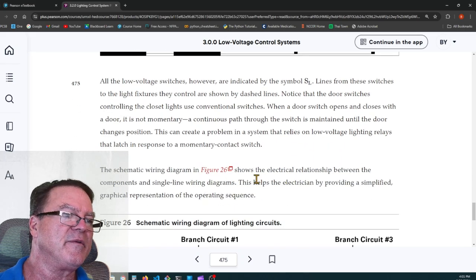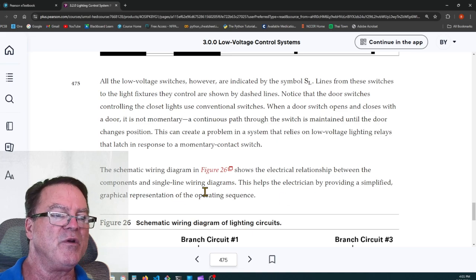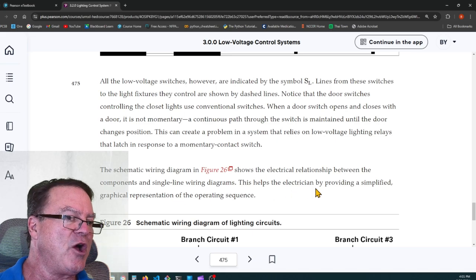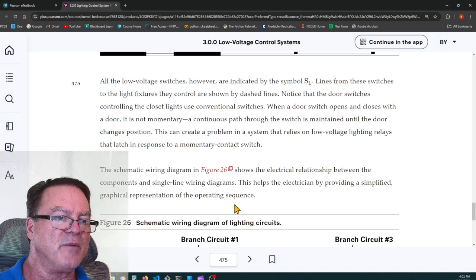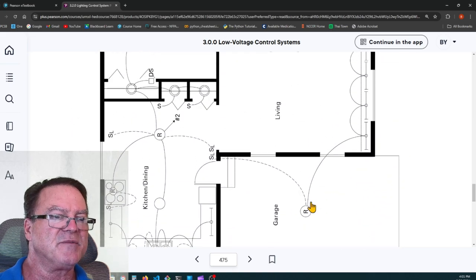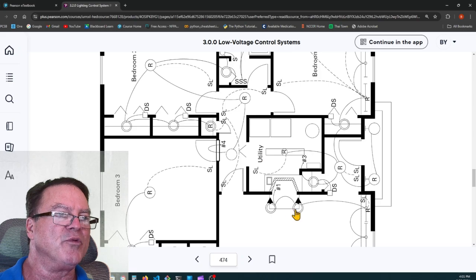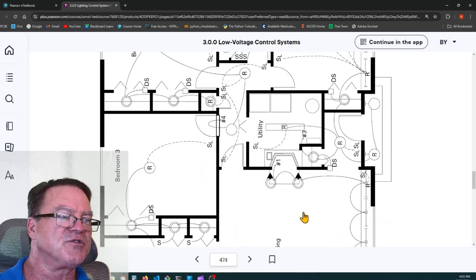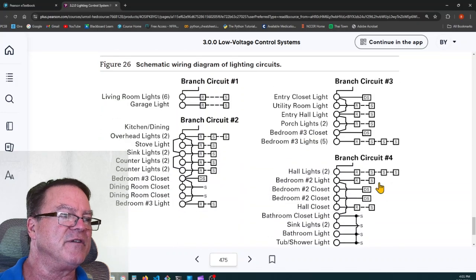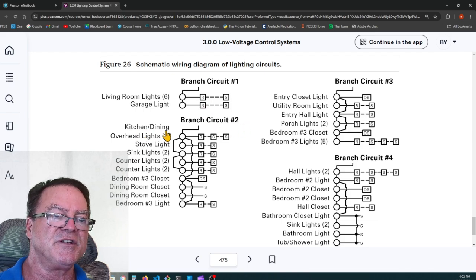The schematic wiring diagram in Figure 26 shows the electrical relationship between the components in the single line wiring diagrams. This helps the electrician by providing a simplified graphic representation of the operating sequence. So they're saying that sometimes it's hard to follow these blueprints when you have regular switches and low voltage switches. So they've made it into this kind of a one line diagram that tells you the different circuits, circuit 1, 2, 3, and 4. And circuit 1 does the living room lights. There's 6 of them, all controlled by a relay, controlled by a low voltage switch. And the garage light is controlled by a relay, controlled by a low voltage switch. So here, branch circuit number 2 is in the kitchen and dining room area.